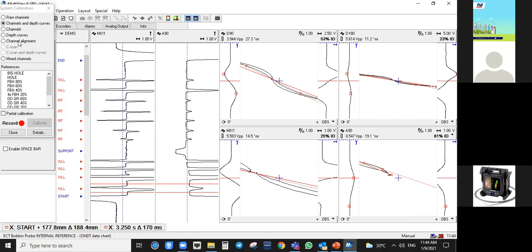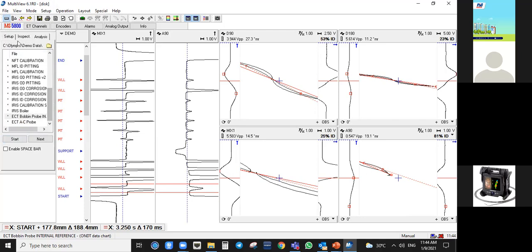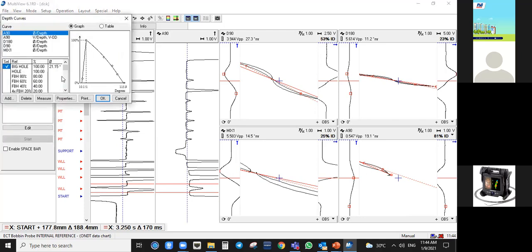So if you would check the depth curves, oops, sorry, close this one first. So this is a common depth curves, okay. So for A90, he used big hole, OD groups, and then the ID groove of 10. So you'll have this, okay. So usually depth curves are like this, except for A90, VOD. The depth curve for this one is just straight, okay. Here you'll see the 10% ID. This is the angle. And then you have your big hole here, 100%. And then 60, 40, and then 20% OD groove.